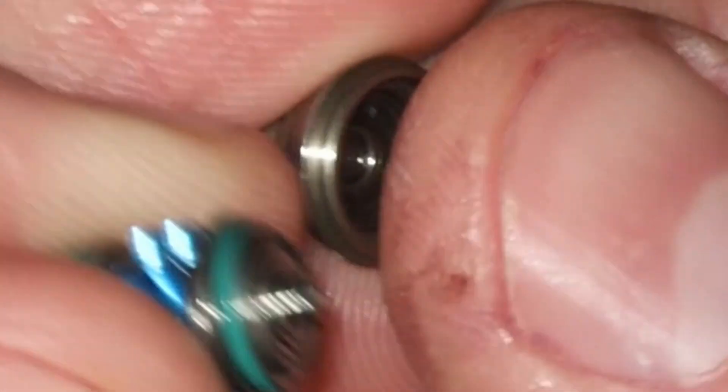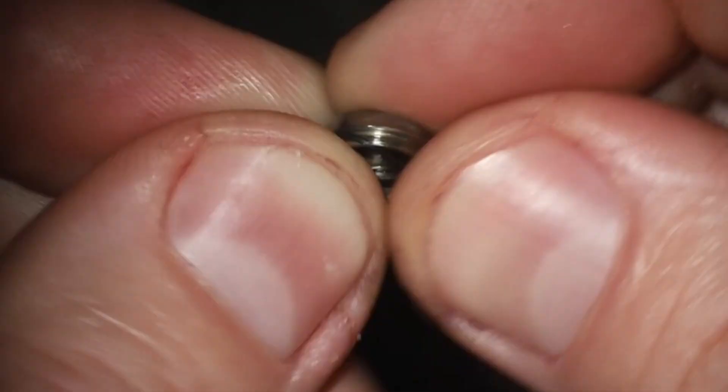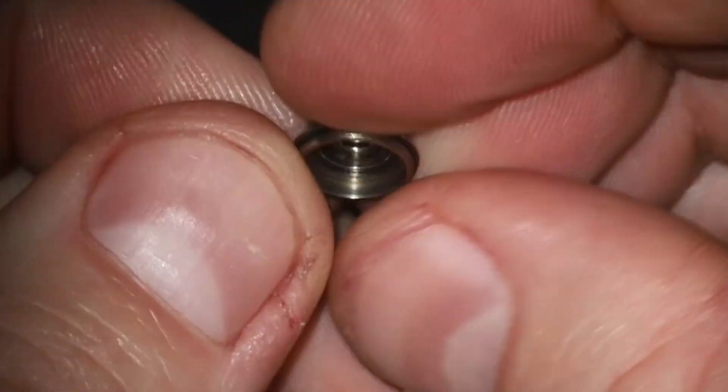You'll also sometimes notice a missing o-ring on the back cap, as in this case. I put a link in the description below for my preferred site for these specific handpiece repair parts, as eBay isn't very reliable for carrying these. You'll also want to put that back on the cap so that there isn't any leakage out the back when you're using it.